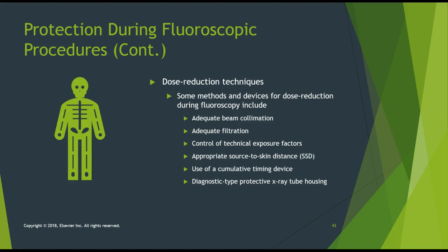Control of your technical exposure factors, so keep an eye on what you're using for your kVp and writing your doses down if possible. Your source to skin distance, you need to watch that. Use of a cumulative timing device. So this device should always be running when that fluoro unit is on so that you can note how much fluoro time has been with that patient. And the diagnostic type protective X-ray tube housing.